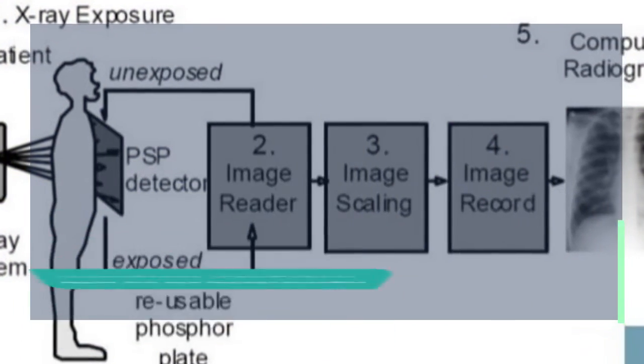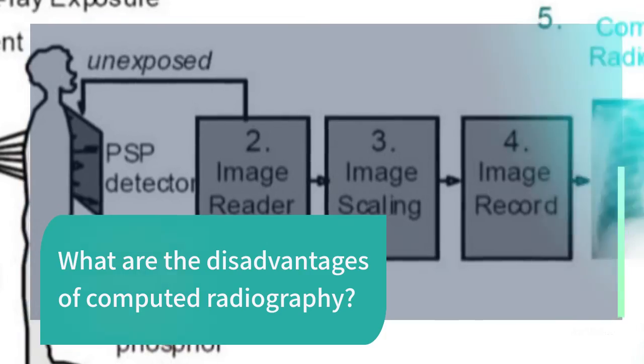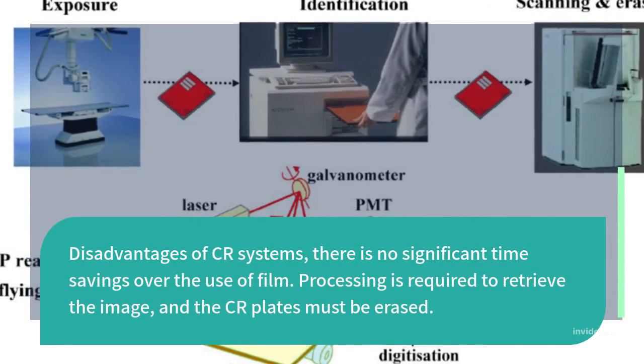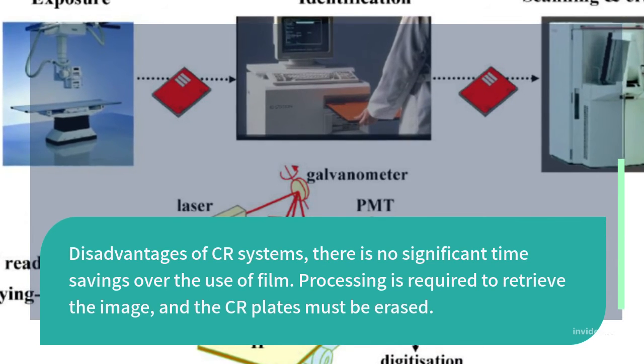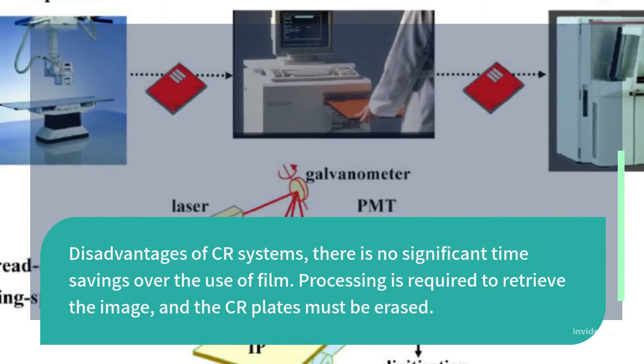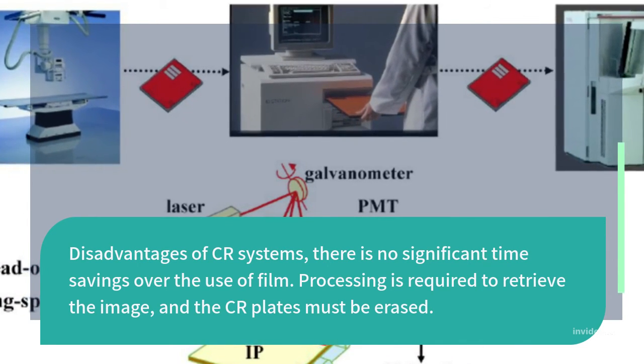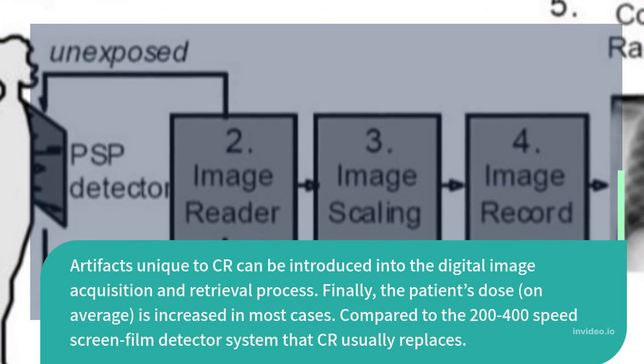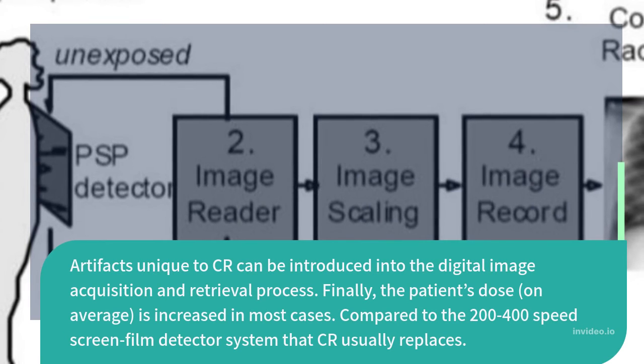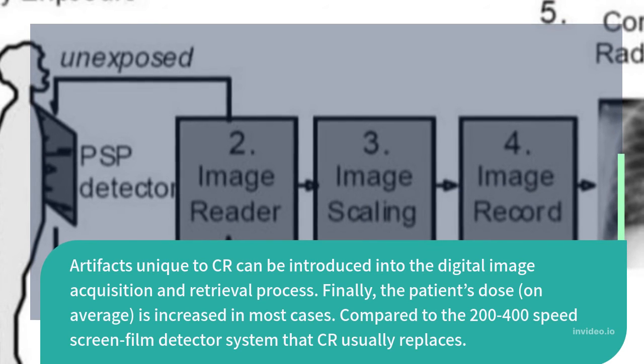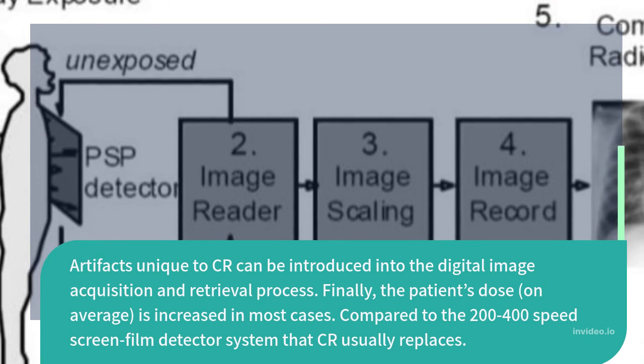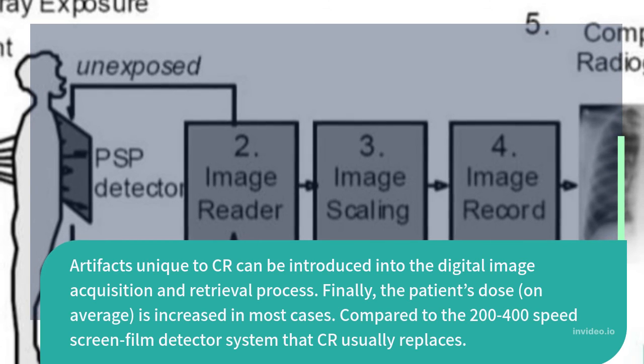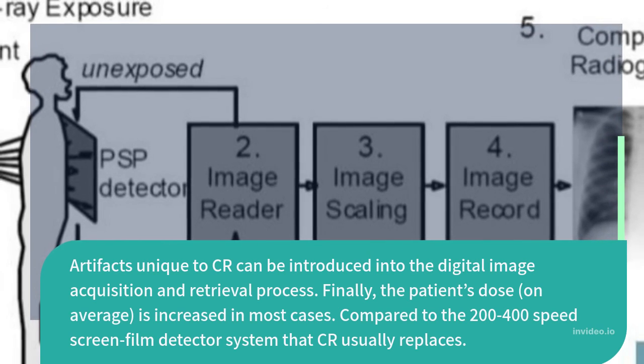What are the disadvantages of computed radiography? There is no significant time savings over the use of film. Processing is required to retrieve the image, and the CR plates must be erased. Artifacts unique to CR can be introduced into the digital image acquisition and retrieval process. Finally, the patient's dose, on average, is increased in most cases compared to the 200 to 400 speed screen-film detector system that CR usually replaces.